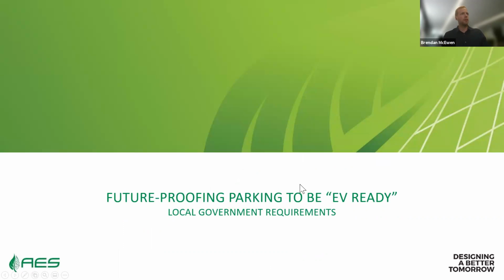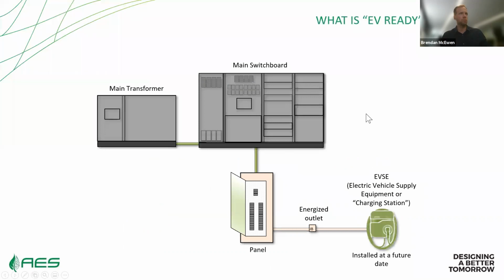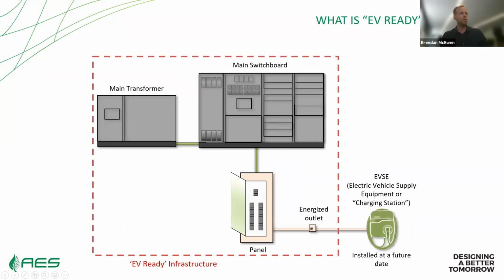In terms of what we mean by EV ready and how local governments have structured these requirements: EV ready basically refers to all the electrical capacity necessary up to a junction box on a branch circuit to install an EV charging station in the future. It's not installing the charging station itself, just having the outlet you can hardwire a station to, or potentially plug one into later, along with the requisite panel capacity and properly sized switchboards and transformers to accommodate that EV charging demand.